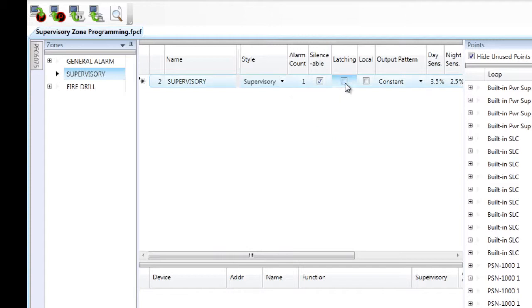In this case, I'm also going to make it non-latching. So in the event that the tamper creates a supervisory event and then resets itself, the panel event will clear without having to reset the fire alarm control panel.